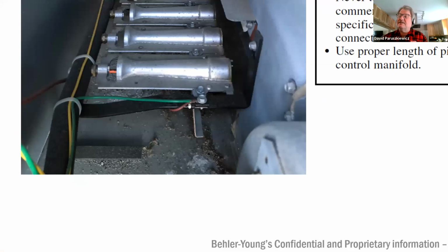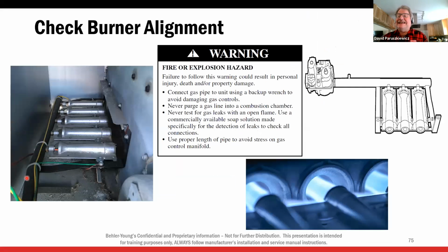and you can see this bar here. This can actually get bent. So now the burners are shooting up slightly or shooting down slightly. Okay, you got to use a backup wrench on that manifold. All right, yes, there's one of those square metal plates that holds the gas valve, but we can still tweak it. But what's even worse is when you've got your piping all together and your union is a little bit short to get to, and you force it and you bend this thing up. I've actually seen this little foot where I can stick my finger on it. It's twisted, it's torqued up so high. All right, so you want to be careful of that.